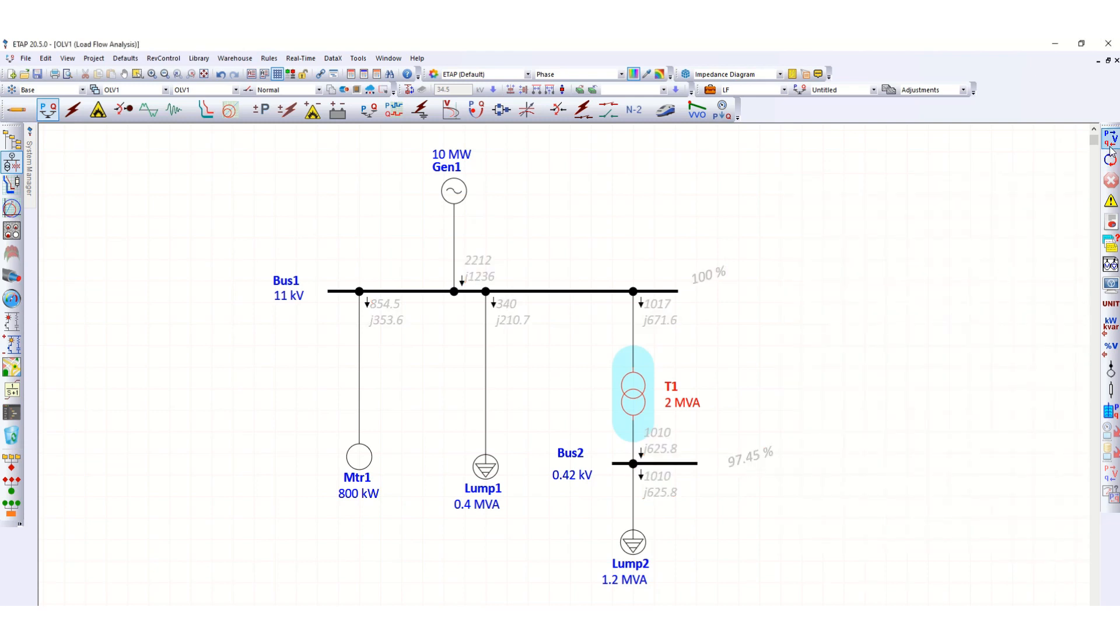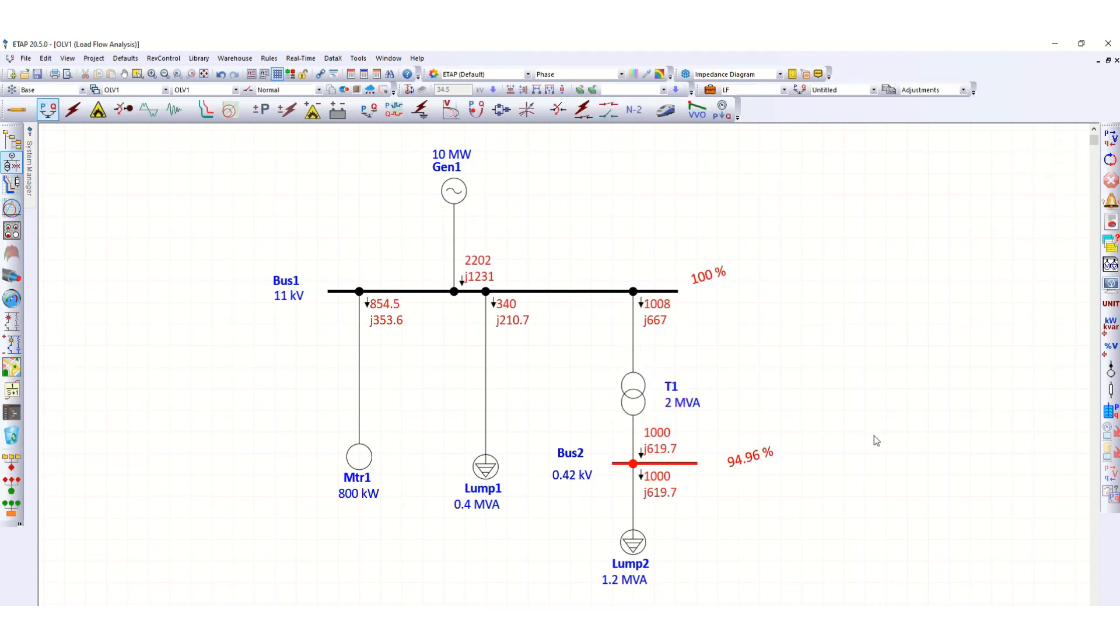So using only that 0% tap, this voltage was 97.45 percent. Now let's run again this load flow. Now it is further down, so 94.96 percent. Previous it was 97.45 percent, so it is now in red color, that means it is now under voltage.